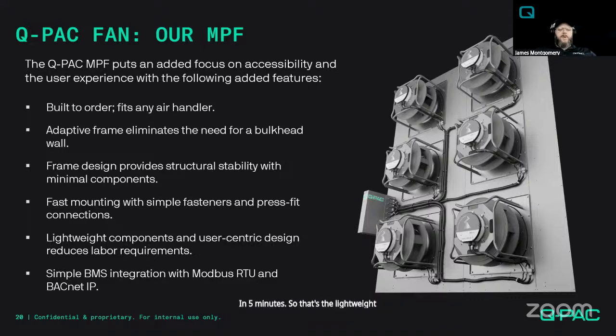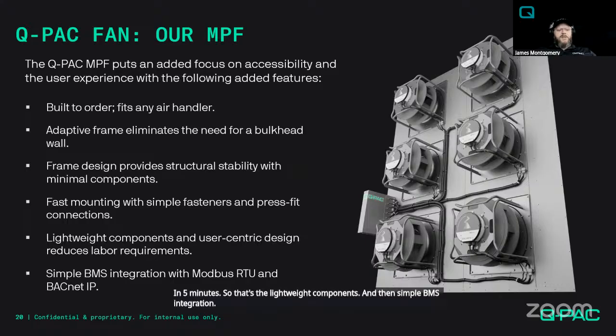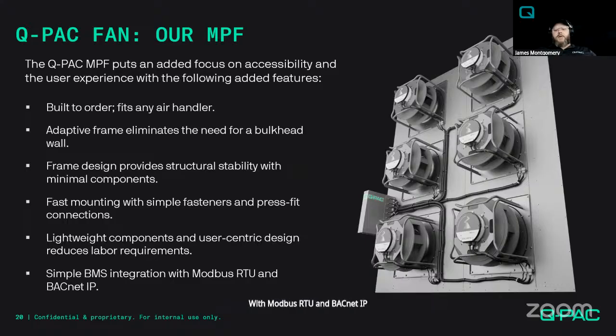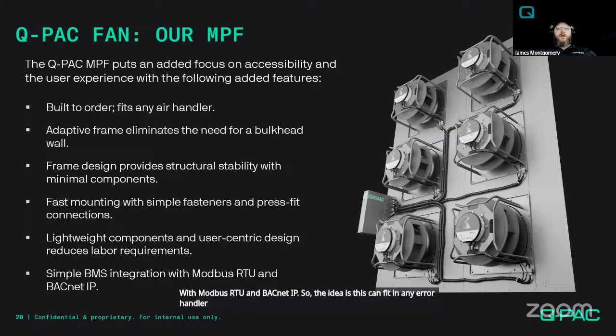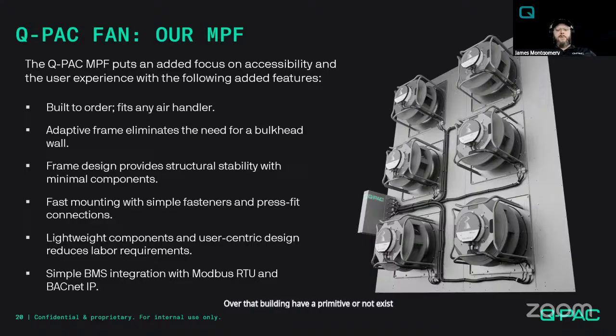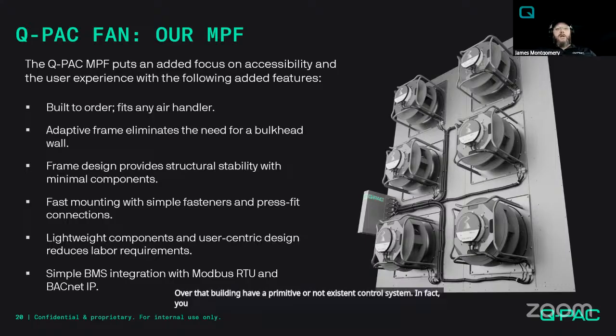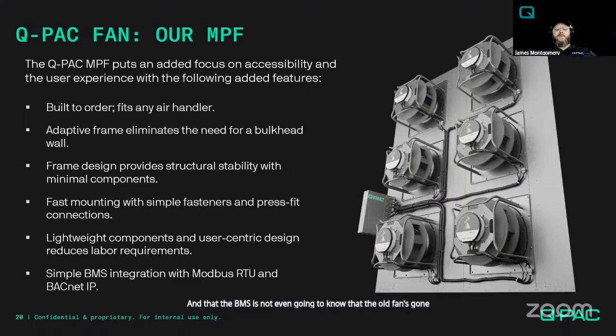And then simple BMS integration with Modbus RTU and BACnet IP. So the idea is this can fit in any air handler in any building, whether that building has an advanced control system or whether that building has a primitive or nonexistent control system. In fact, you install one of these and the BMS is not even going to know that the old fan's gone, the new fan's in there. And we've seen that happen several times on retrofits.